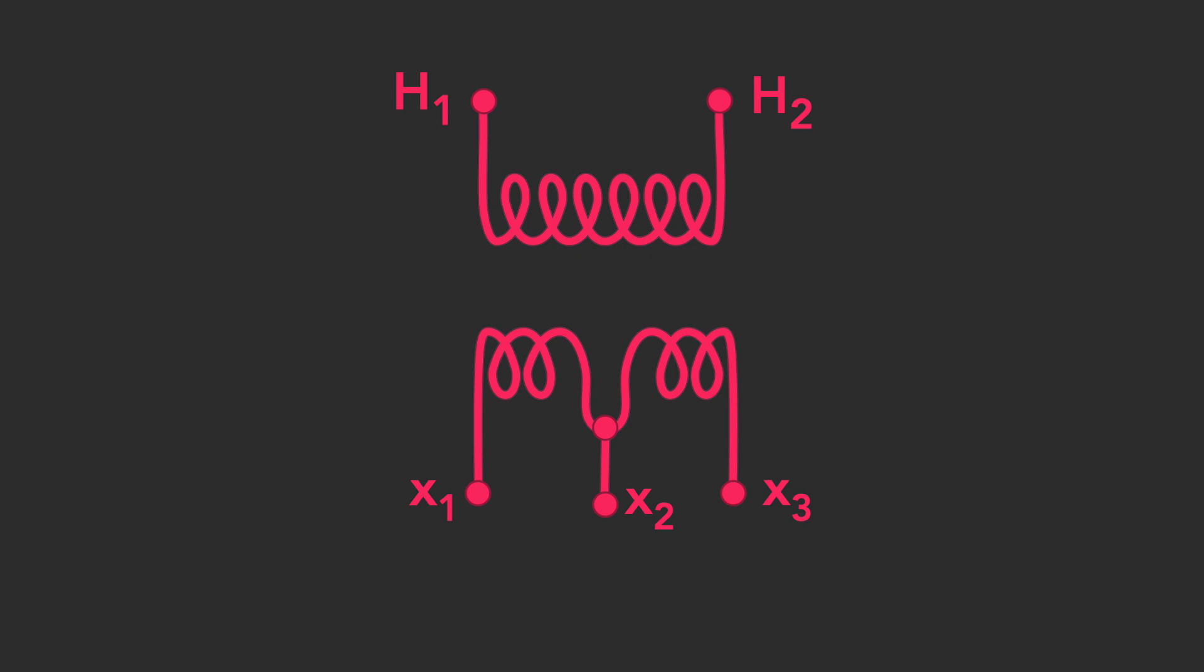In most cases, the X2 bushing has at least two connections on the outside bushing. One connection is to the tank ground just a few inches below the X2 bushing. The second is the neutral connection from the X2 bushing down to the system neutral.